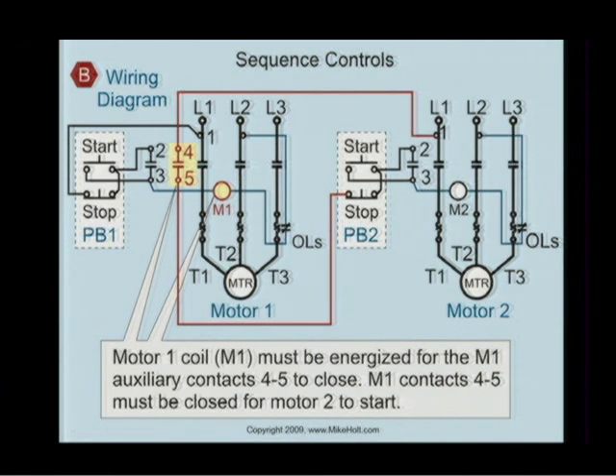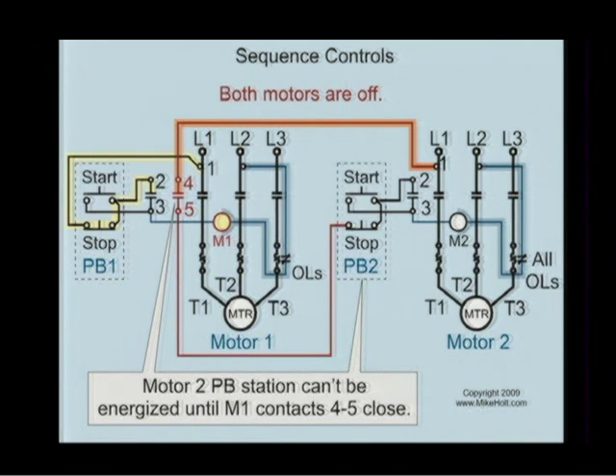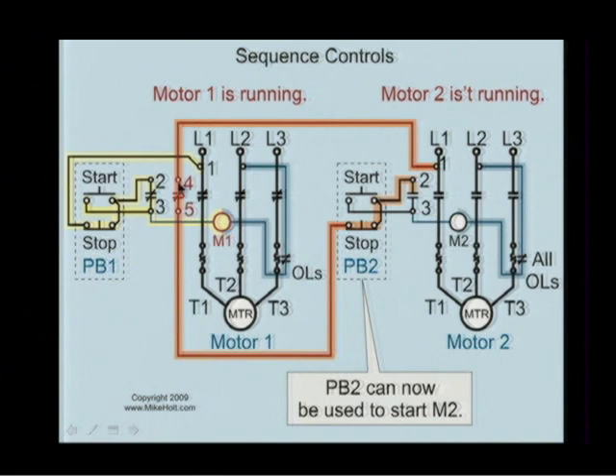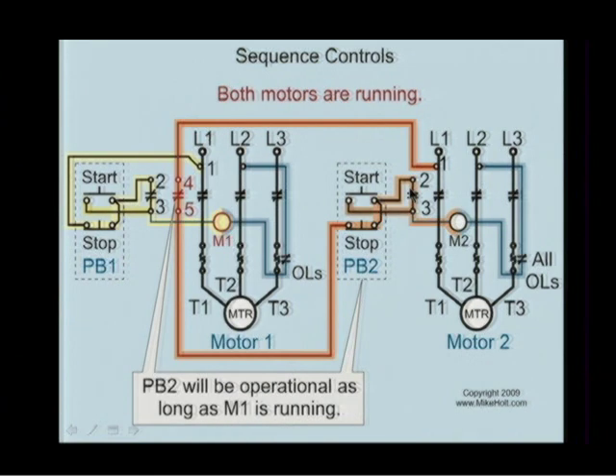Good. I have no problem with that. Makes sense. Yeah, okay, both motors are off. That was our state. And motor 1 is running. So now we have voltage going over to control circuit number 2, and that allows me to press the start button, which energizes motor number 2.